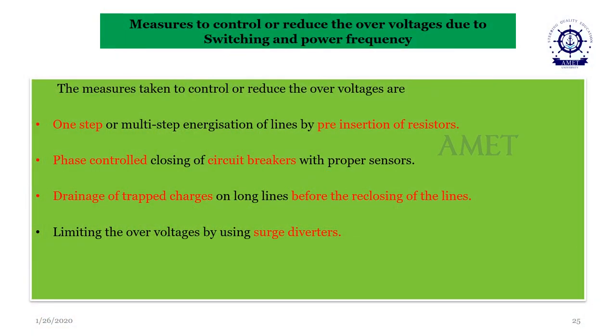Once the supply is off, once the system is not in operation, there will already be some storage of charges. That charge has to be drained off. Otherwise it will be retained in the system, and when put in operation, this will be added up and give a jerk, an initial increase in the voltage, along with the system voltage. So that has to be drained off before any power system operation. That is called draining.